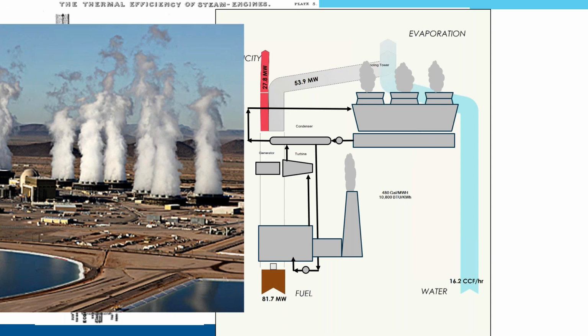On a typical coal plant, at least in Arizona, it takes 480 gallons of water per megawatt-hour to make electricity, roughly speaking. Some plants are a little better, some a little worse. On a nuclear plant, that number is more like 700; it actually takes more water at Palo Verde than at a coal plant. That has a lot to do with the zero discharge requirements for Palo Verde and all the safety considerations, there's a lot more cooling going on that ends up evaporating water.